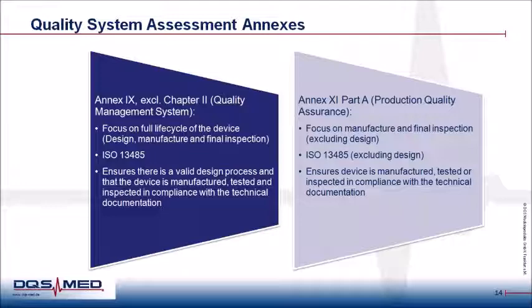Annex 11, on the other hand, is generally used in association with Annex 10, or in combination with technical documentation Annexes 2 and 3 for low-risk devices. It is based on ISO 13485 without considering design, considers only the manufacturing aspects and inspections, but not the design, and confirms that manufacturing and inspections are aligned with the technical documentation.